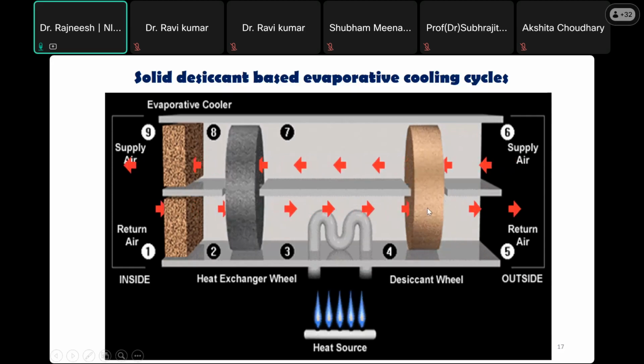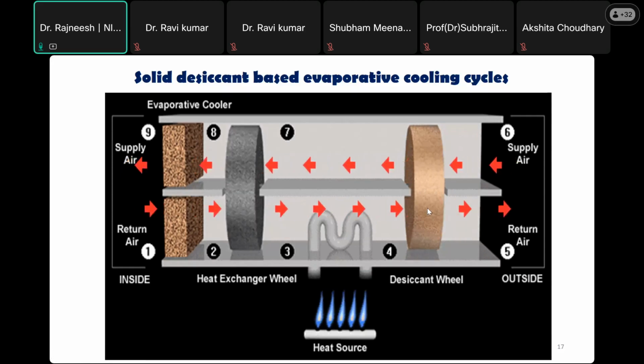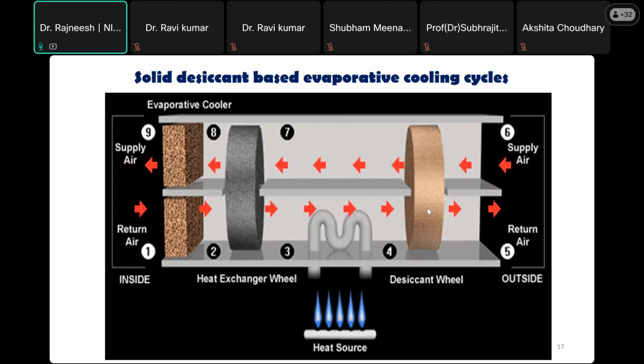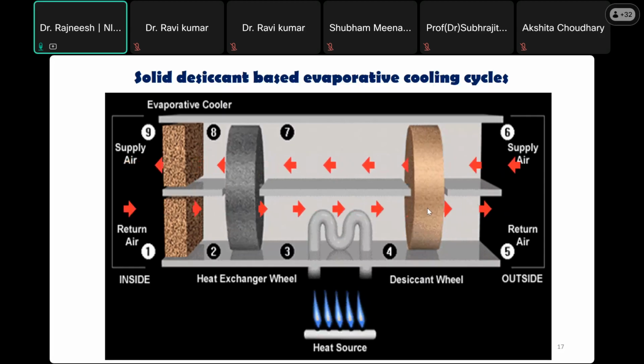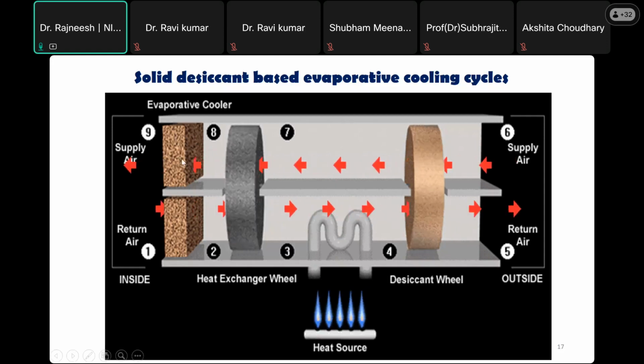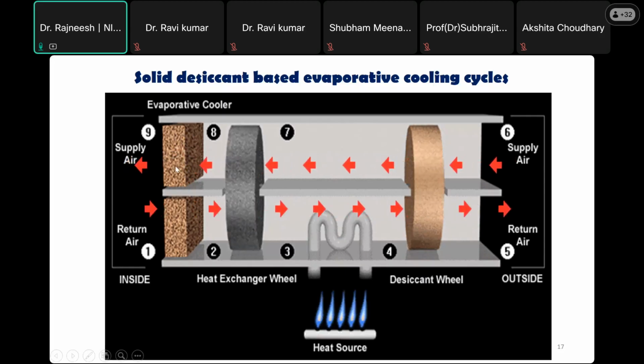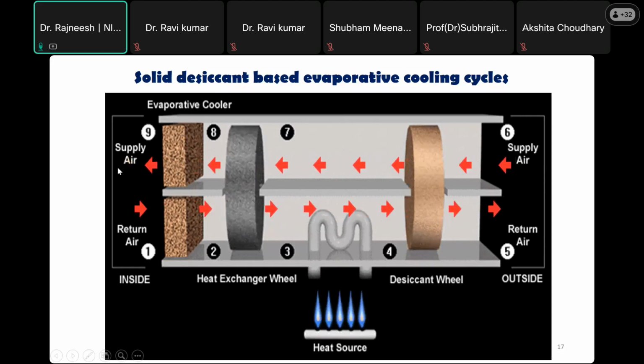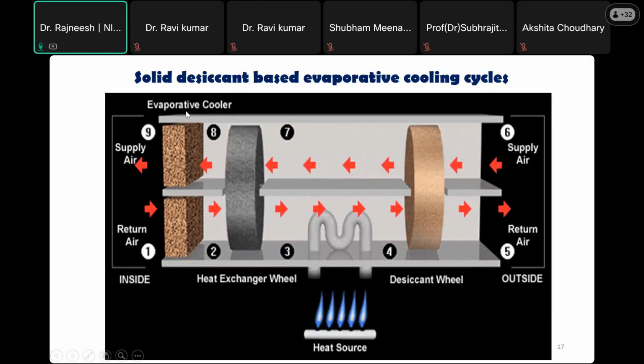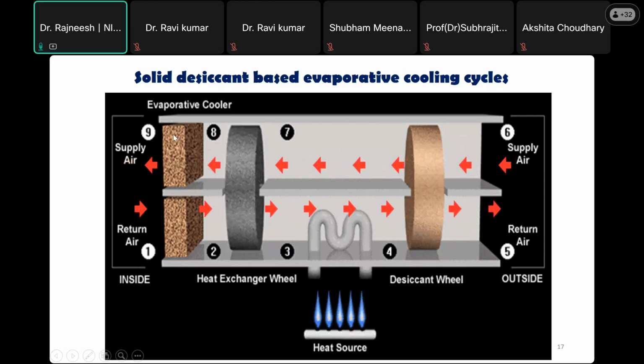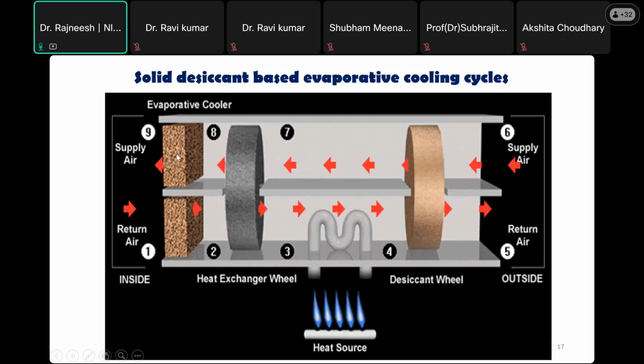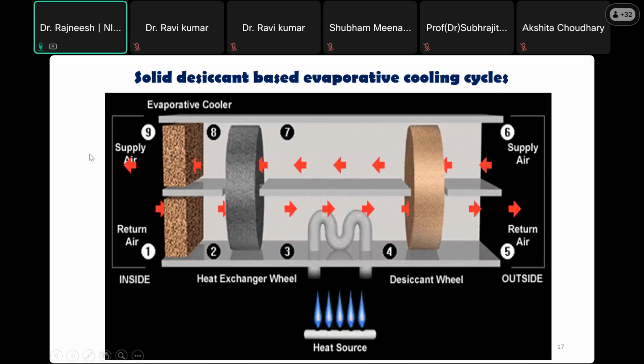As I mentioned in the previous slide, a regeneration temperature of 45 degrees C is required only for the liquid desiccant material to get regenerated. So that is the kind of limitation of the solid desiccants: we need more temperature to get the desiccant regenerated. Now we need to increase the moisture of the air a little bit, as most of the moisture is taken up by this desiccant wheel. To get the comfort conditions, we need to add a little moisture. For that purpose, we are using this evaporative cooler, like a desert cooler we use in households. So a little moisture content will be increased, and ultimately at point 9 we'll be getting the comfort conditions.